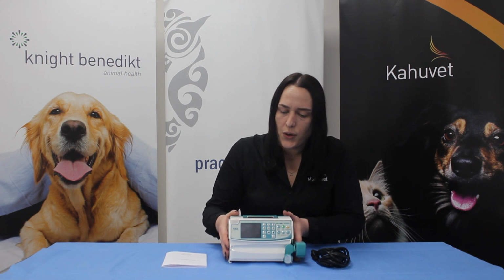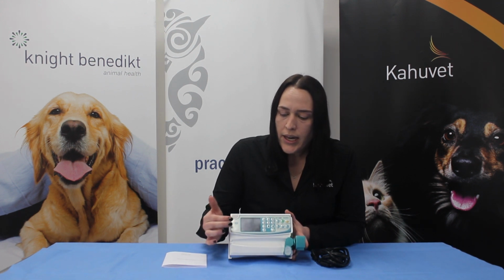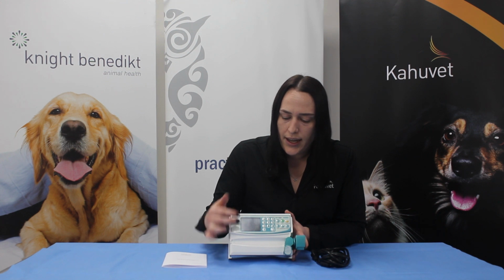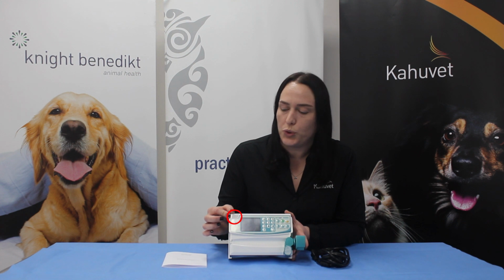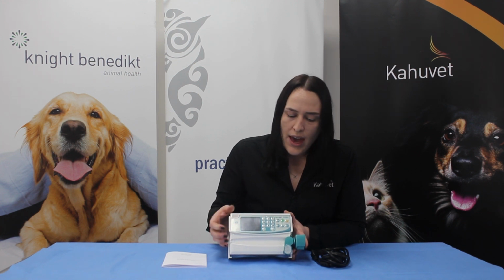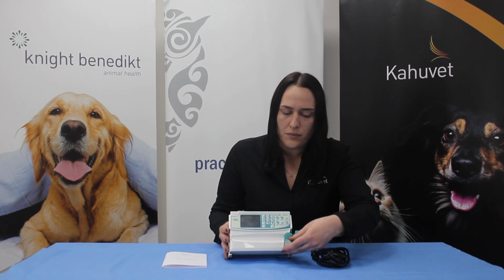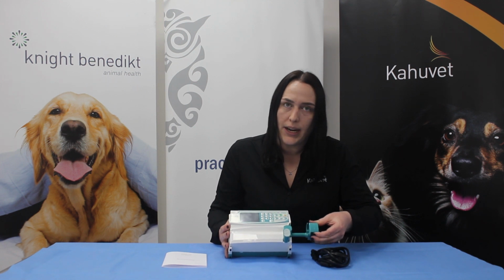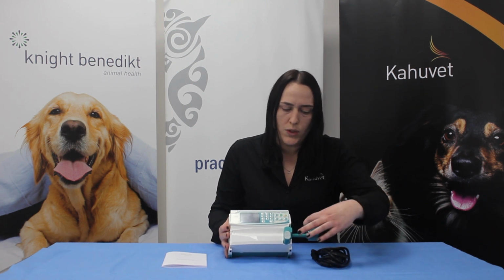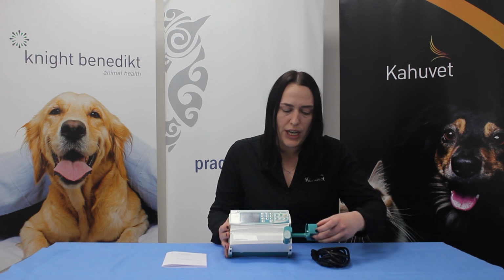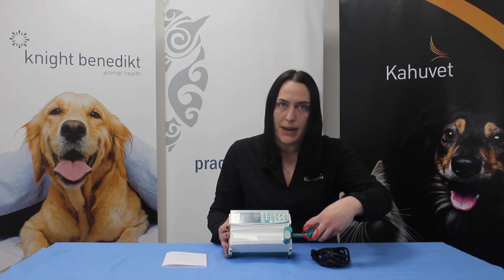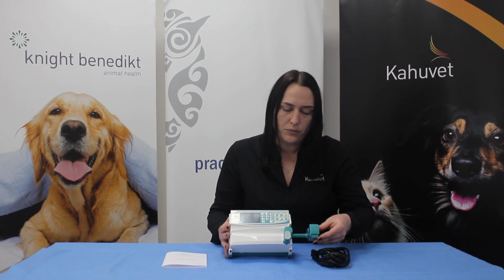And to the front of our unit, we have our display screen here with our control panel. We also have our LED light here in the corner, which will alarm for occlusions and other types of alarms. We then have our plunger control, which is just released with a button under the rear here. And that controls the holding device for the syringe plunger. It also has this white release button here. If we're needing to reset, we can do so by just pressing in that white button.